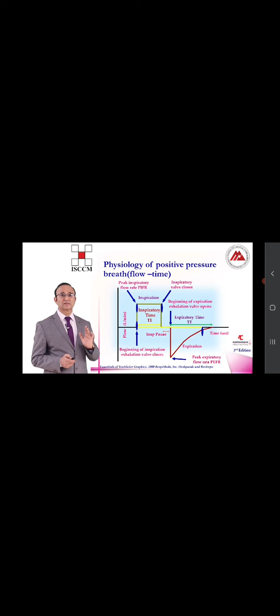One thing I would like to say here is that expiration is a passive process. It is not controlled by the ventilator. Whatever mode you give, the expiration will appear the same. Whether you give a volume preset mode or a pressure preset mode, the expiration will be passive and will appear the same on the flow time graphics.